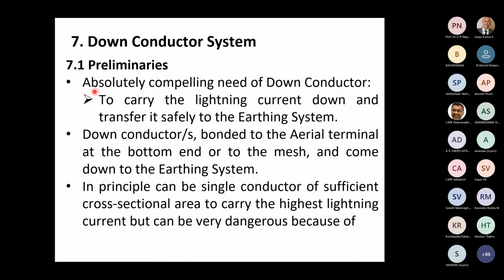Now, I'll have to emphasize again, it's absolutely compelling to have a down conductor system because the lightning current has to be taken down very safely. Otherwise, supposing lightning is attracted to the top of the rod and then the current flows through the building, it's a disaster invited. Let me repeat once again, it's a disaster invited. Therefore, to avoid this, we have provided the lightning terminal. That lightning terminal must be connected through a down conductor to the earth system so that the lightning current flows very safely.